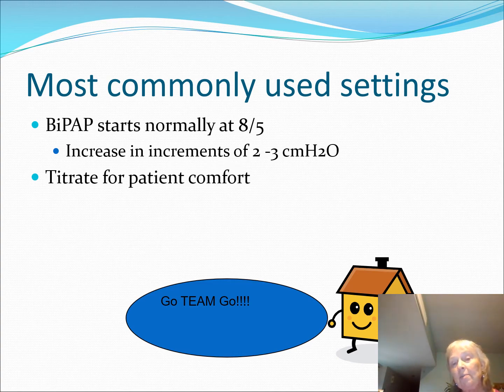So normally we start around 8/5, and then we're going to increase them in increments of 2 to 3 centimeters of water pressure. And it depends on what we're trying to do. If this patient has a lot of CO2, in some cases, if their oxygenation is okay, we'll say, okay, let's go from 8/5 to 10/5, or let's go to 12/5, okay? If there's an oxygenation issue, then let's bring that IPAP up to 10, and let's bring that EPAP up to 7, okay?